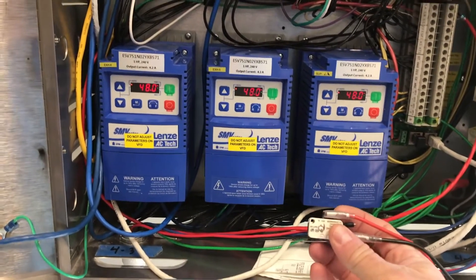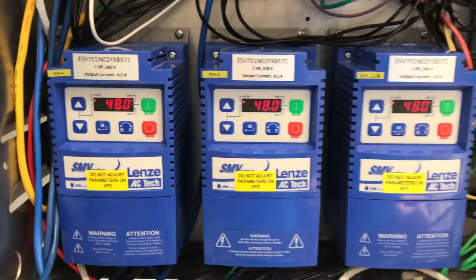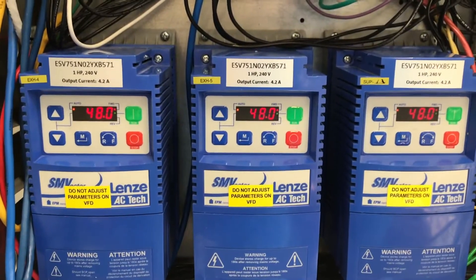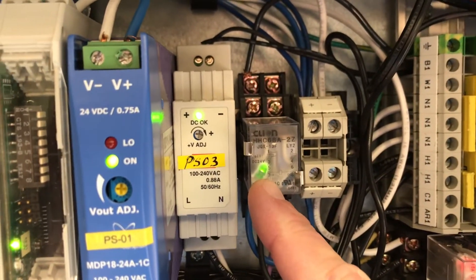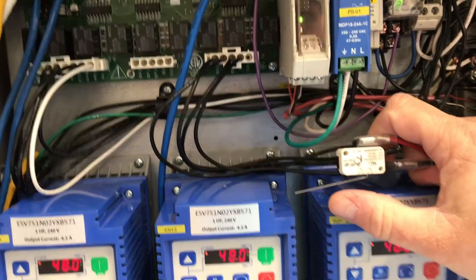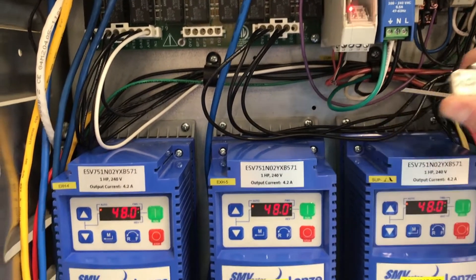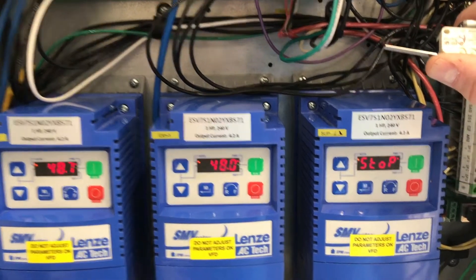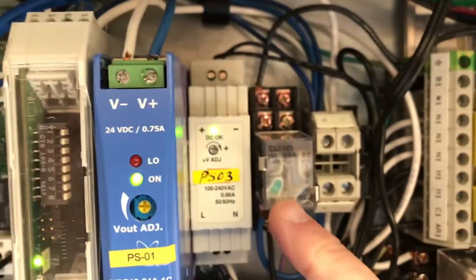Now we're going to look at it again with the hood turned on. All three VFDs are running at 48 hertz — my two exhaust VFDs on the left and my supply VFD on the right — and my lighting relay is energized, meaning my hood lights would be turned on. So if the Ansul system gets triggered, the supply VFD will go to stop, my exhaust VFDs will ramp up to full speed, and my lighting relay will be de-energized, turning off my hood lights.